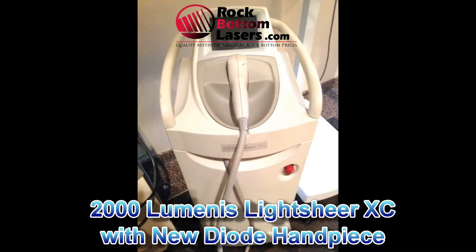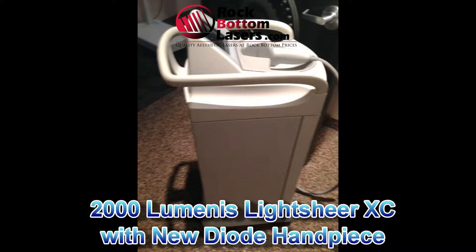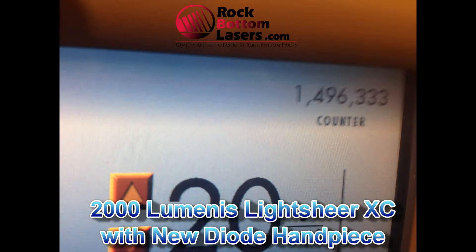Hi guys, this is Vin Wells here with rockbottomlasers.com. What we have here is a 2000 Lumenis Lightsheer XC. It is a 100 millisecond unit. It has excellent headroom. The handpiece diode was replaced in 2013 and so the headroom on it on auto is 1.73, which is outstanding.